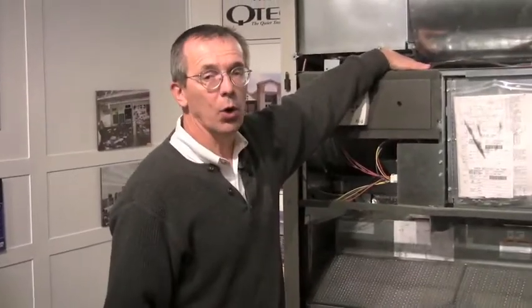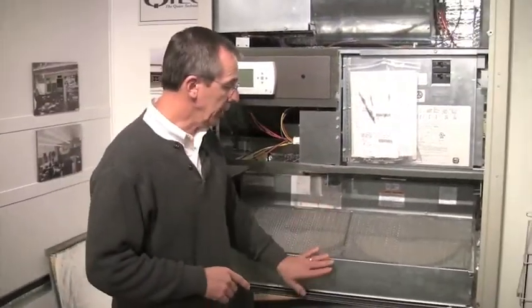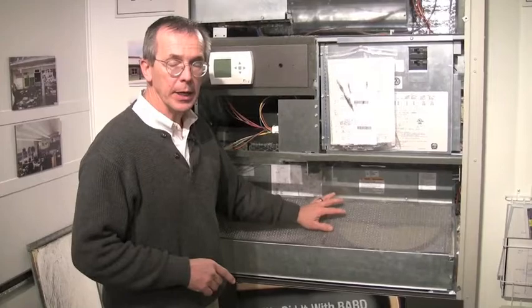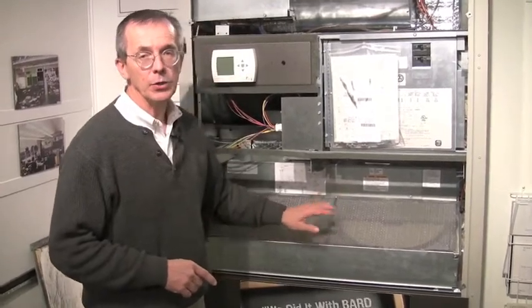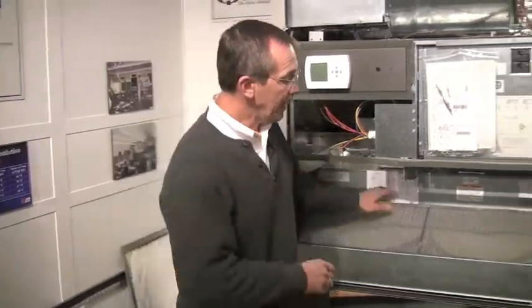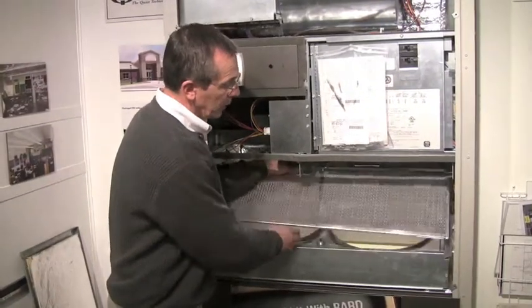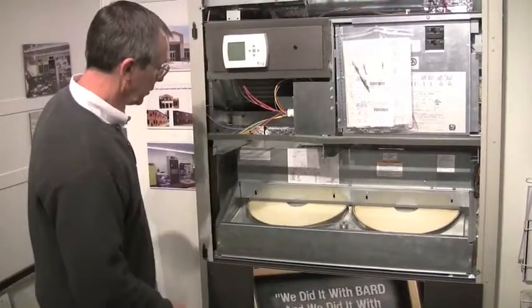The hot gas coil is mounted to the back of the condenser coil. Bard offers 2 ventilation packages that meet ASHRAE standards. One of them is a CRV. The CRV is a commercial room ventilator. If this unit had it, there would be a damper here and a damper here with a motor here to control the damper to force air in and out of the classroom. This happens to be the energy recovery ventilator with a pre-filter.